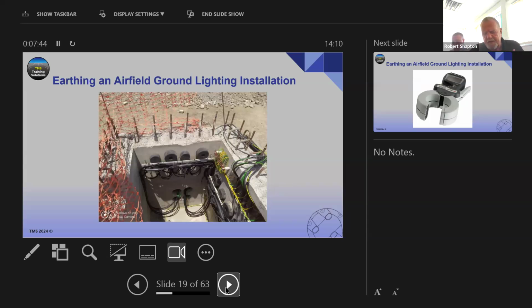And the last thing that comes into play is the testing of earth circuits. Now, Kevin, a bit later on, will go into detail on how testing is carried out, but realistically, testing should be carried out at least, and I say at least, once every 12 months. The results should then be compared with the initial installation results and also any previous tests, in order that you can see if there is any degradation on the circuit and how the general circuit is holding up.